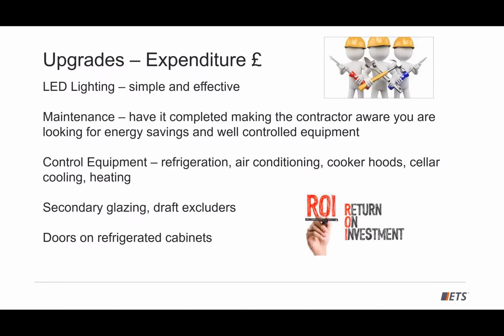I was going to bring up pictures of poor maintenance activities on sites, but you've probably all seen them - condensers outside from your refrigeration all clogged up after a contractor has just been. They've got to keep the equipment clean, even the stuff you don't see, like behind self-contained chiller cabinets, because that's where your condenser is. Airflow across your equipment and chilled cabinets is very important. Overstocked cabinets waste cold air, and then you have to replace that.